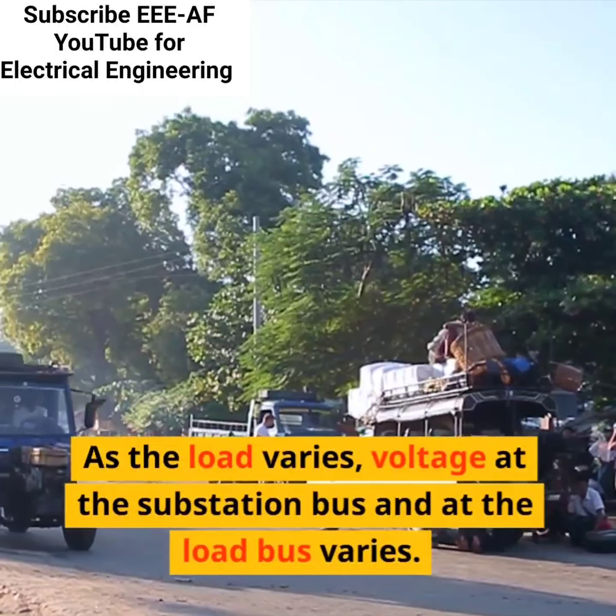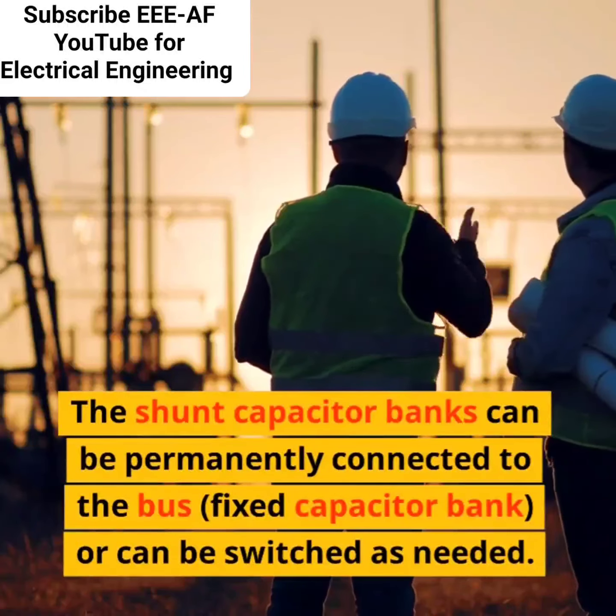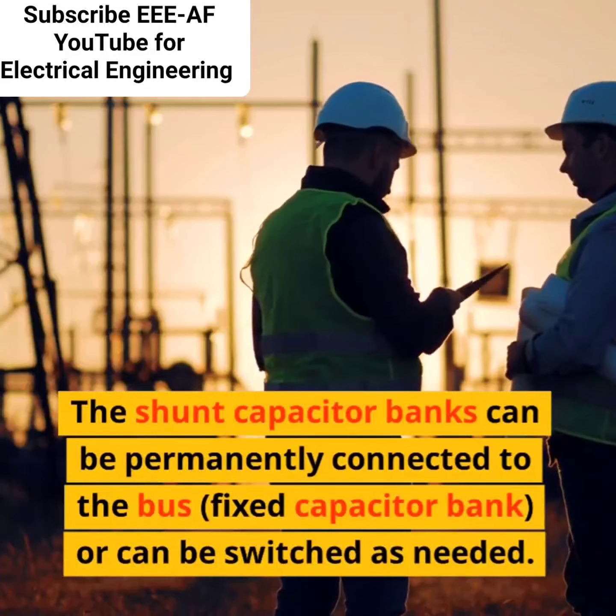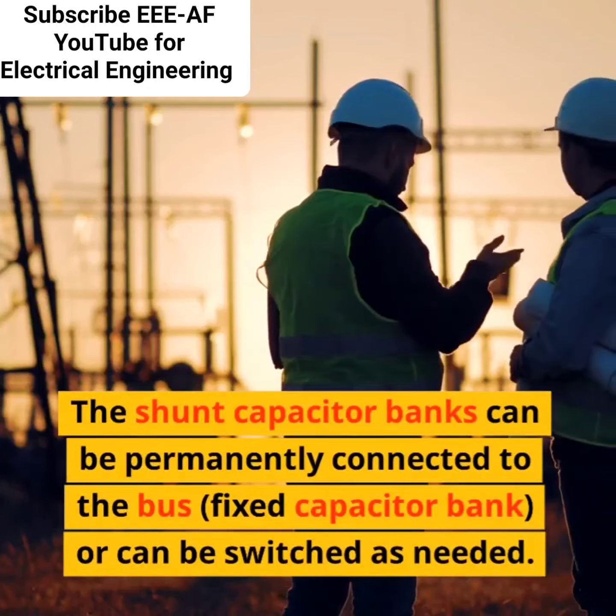As the load varies, voltage at the substation bus and at the load bus varies. Since the load power factor is always lagging, a shunt-connected capacitor bank at the substation can raise voltage when the load is high. The shunt capacitor banks can be permanently connected to the bus, fixed capacitor bank, or can be switched as needed. Switching can be based on time, if load variation is predictable, or can be based on voltage, power factor, or line current.